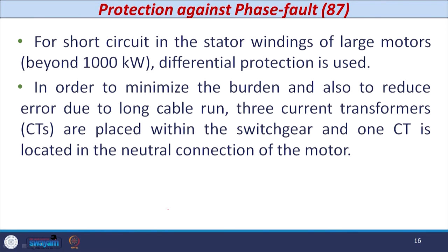The next phenomenon is protection against short circuit — basically phase-to-phase faults — and the relay number given is 87. For short circuit in the stator winding of large induction motors (beyond 1000 kW), differential protection is used. Whereas for small or medium range induction motors where differential protection cannot be used, IDMT relays or instantaneous relays can be used because these relays are cheaper than the differential relay.